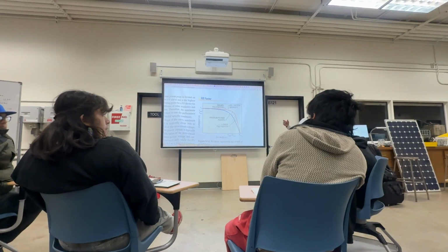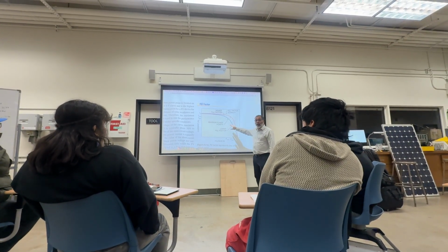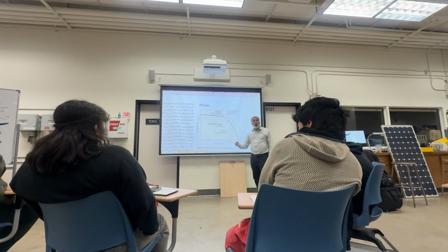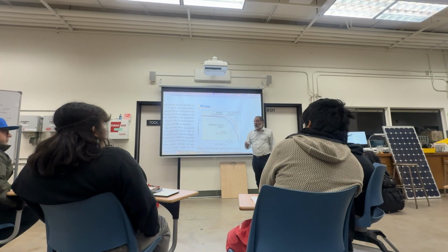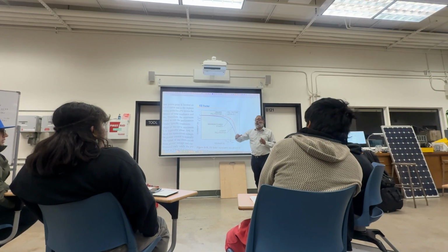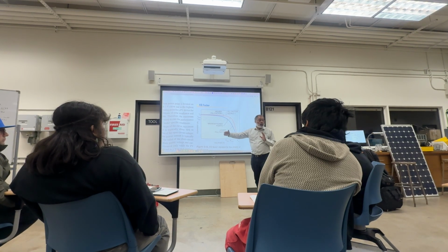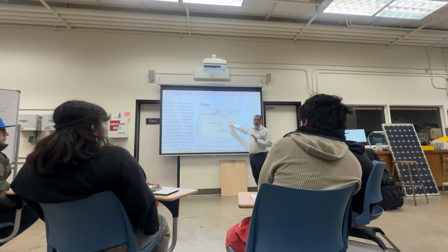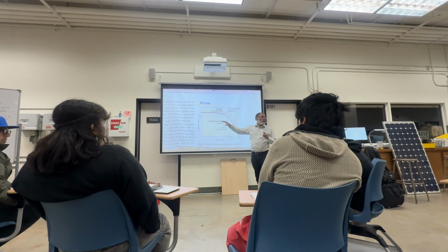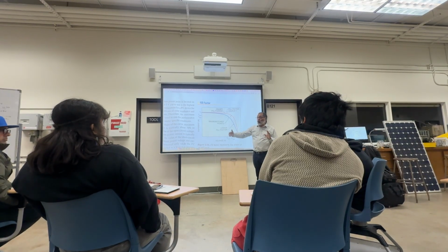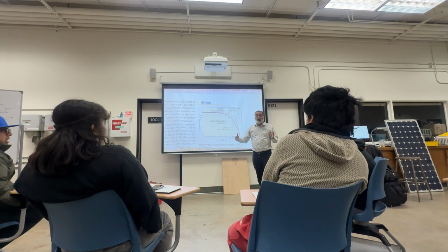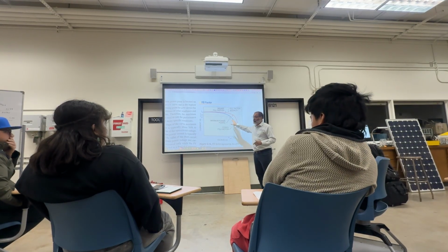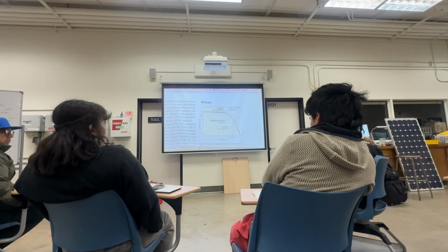So what this could be telling us, if we take a look at it in an IV curve trace, is that we don't have large enough conductors. We put very small conductors in there that have a lot of resistance and we're sufficiently far away from the inverter. That's what this is going to tell us. And that's bad. So that's why you want to keep your voltage drop down to between like 2% or even less than that, so you don't impact the fill factor.